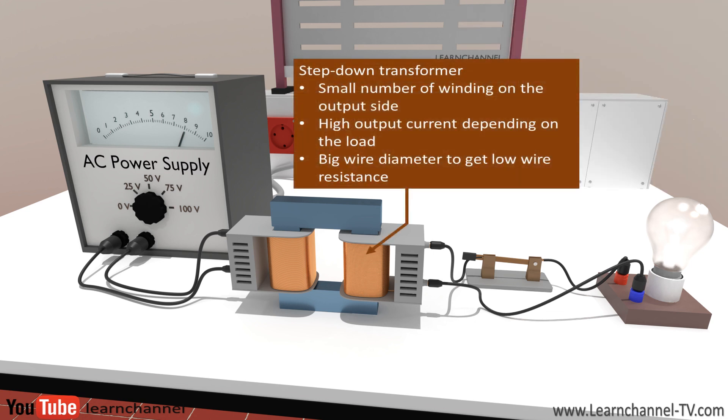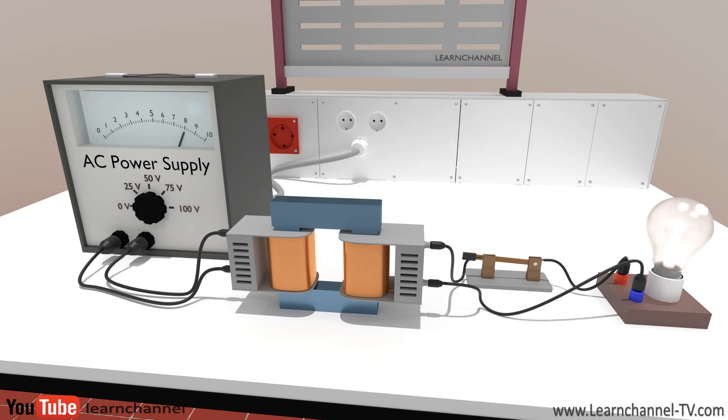We should mention at this point that the secondary winding of a step-down transformer has a bigger wire diameter than the primary winding, because you need low wire resistance for the high current you can get at the output, and vice versa, a small diameter for the secondary winding when you have a step-up transformer.